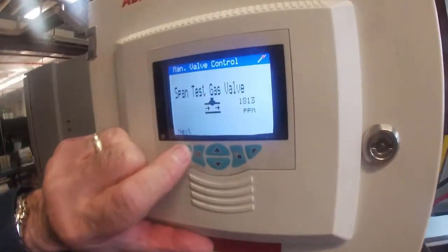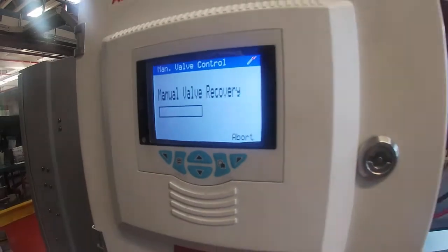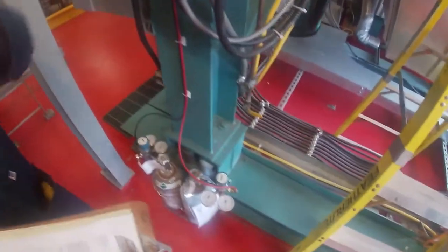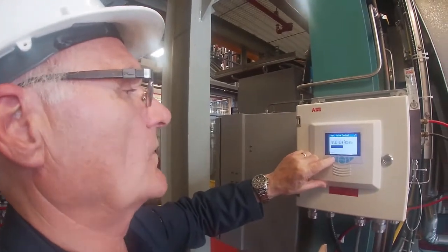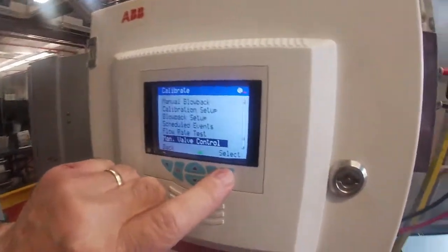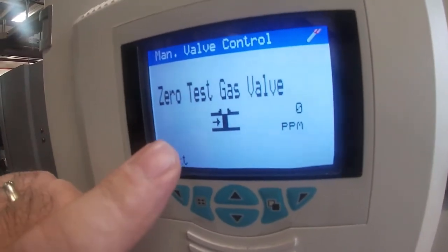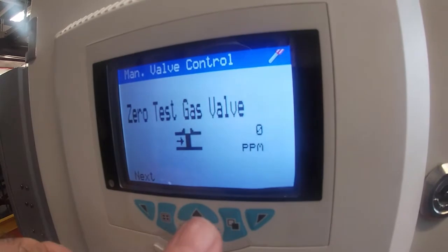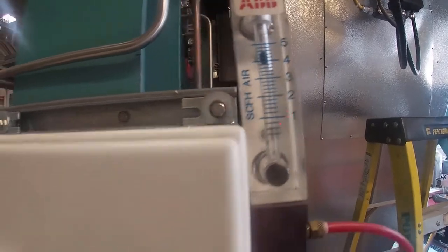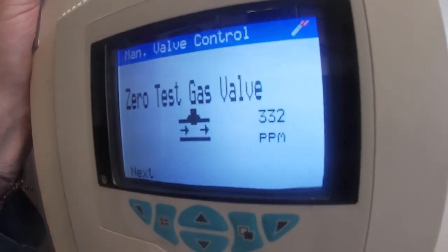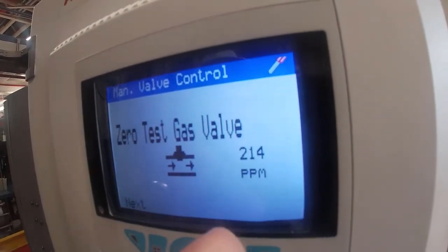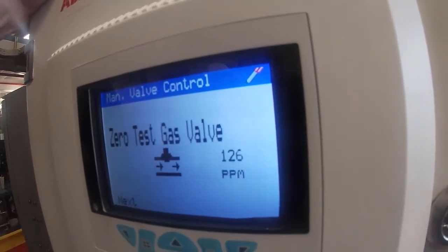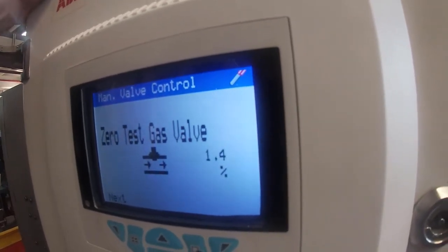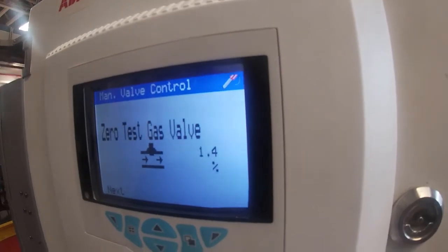So then what I'm going to do is go next. It's doing recovery. I'm going to switch bottles over down below here. Okay, so I'm going to go to next. I'm going to go back in again, select manual valve. This time I'm going to do the zero gas. I've opened my zero gas bottle, sample lines up. So I'm going to inject it. And you can see right now that the O2 was at 20-odd% and it's dropping like a rock. The CO was up quite high and it's coming down. You can see it at 214 now. On the next scan it'll probably be lower, 126. And our O2 at zero gas should be around 1.01 and no CO.